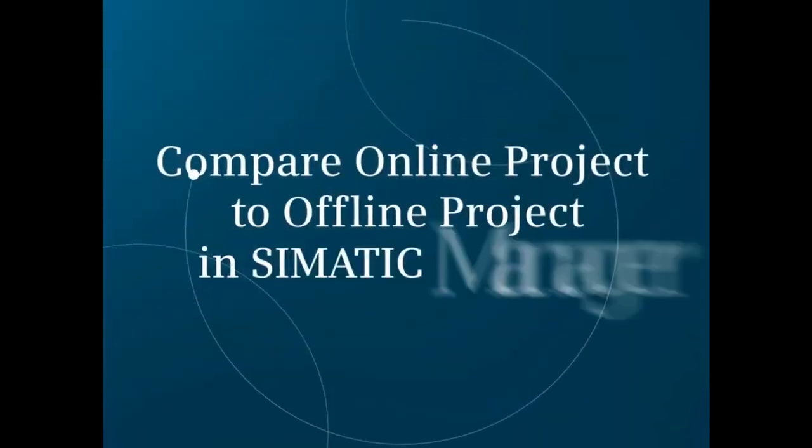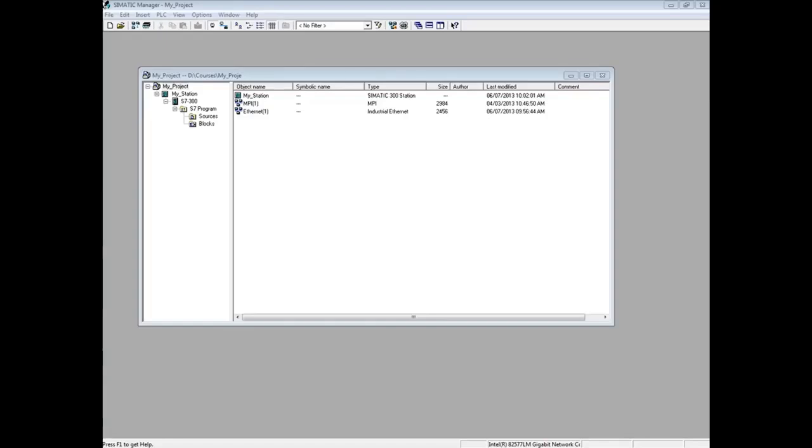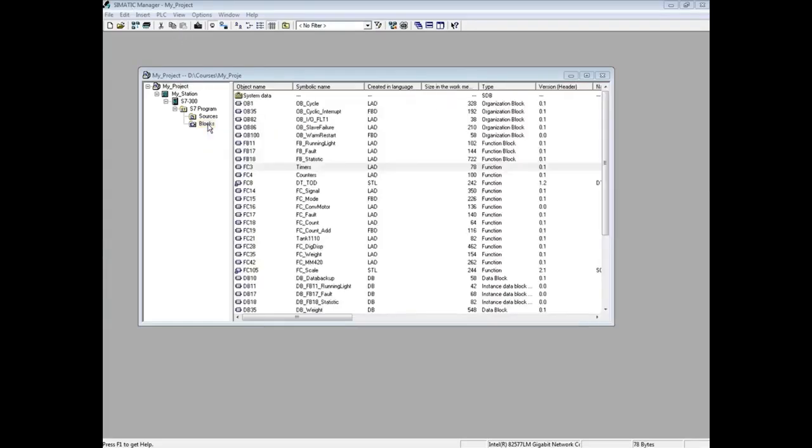In this video, you will see how to compare an online project in the PLC to an offline project in SIMATIC Manager. The programming editor must be closed to perform a block comparison. To begin, be careful to highlight the blocks folder. If a single block is highlighted, only that block will be compared.